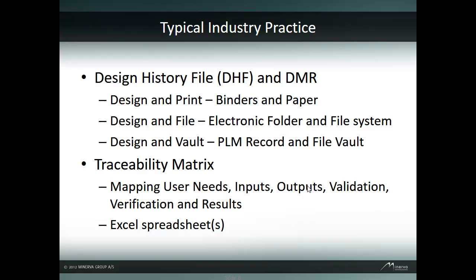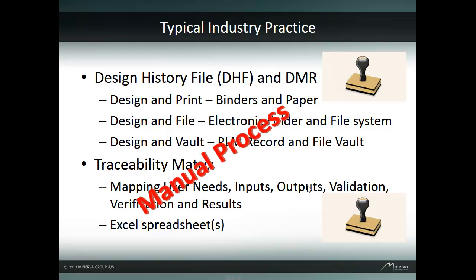Since it is a regulation to have a DHF and DMR, the typical industry practice is to design and print, meaning to do the design and then print to paper and store in a physical binder. Some design and file, meaning that they store the electronic file into a file system that is structured to look like a DHF binder. Others use PLM-created structured document records, mimicking the design history file binder and managing the files in the PLM vault. To keep track of traceability of user needs, design inputs and outputs, and their validation and verification plans along with the results, a common industry practice is to utilize Excel spreadsheets. In all cases, this is a manual process that is very labor-intensive and error-prone. Even if the product is correct, having data that is incomplete or at the wrong revision can trigger problems with an audit.